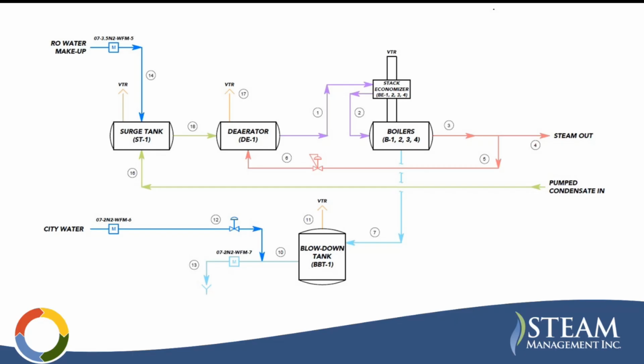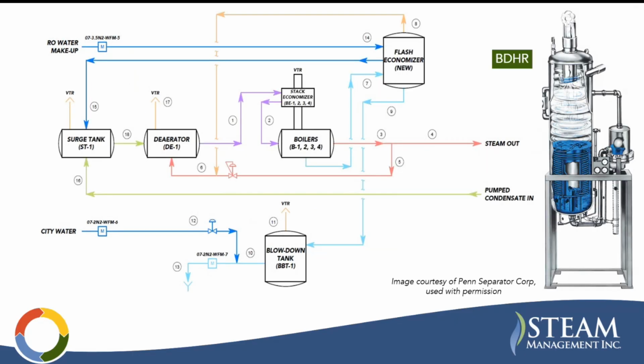Here's the system again, just as a refresher. So again, we're going straight to the bottom blowdown tank. What is different with a blowdown heat recovery system is it's going to look like this. So your blowdown, again, this is surface blowdown, not bottom blowdown. Bottom blowdown is not really shown here. It's just not relevant for a heat and mass balance. So surface blowdown is going to go into your flash economizer. That's this on this example unit here. That's this inlet. So you're going into your flash tank. Some of that steam is flashing off. You're going to use that in your deaerator.